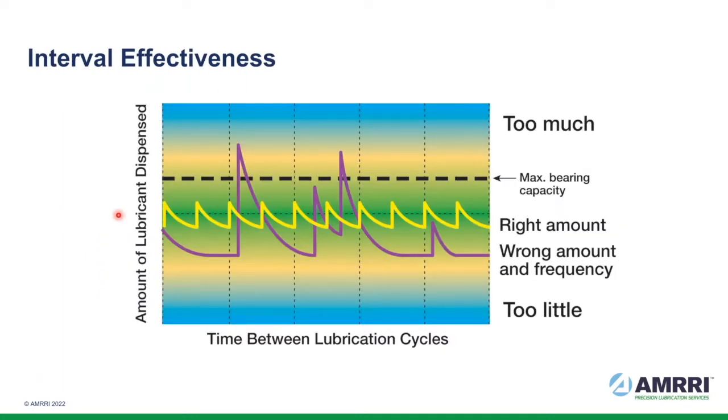Next question is one of how often should we feed? Now, for a given bearing, we might want to feed more often or less often, depending upon operating conditions. The faster it's running, the larger the component, the more often we're going to need to feed the bearing or check the level on the bearing to assure long-term productivity. Without a calculated value, we end up with intervals and volumes that are pretty unsteady. With the calculation, we have a starting point that gives us the means to be very accurate in identifying how often we should go about replenishing that small quantity of grease. And then, of course, we can validate that with our sensory tools, ultrasonic energy detection.